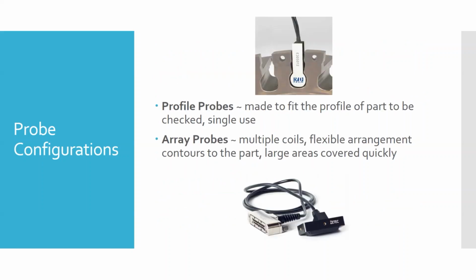Here are some of those profile probes that I talked about. Here's one where the probe is embedded in typically a plastic piece that's designed to fit the shape. In this case, it's like a turbine disc or a compressor disc. It's a bulb style blade root where the blades would key in there. We want to make sure, for instance, that we're not getting cracks between these tabs that form the different bulb cavities.